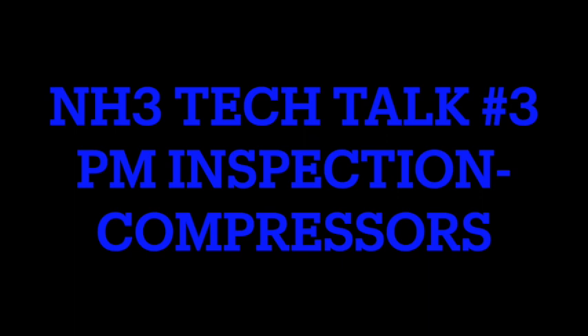If this compressor has an oil pump, a lot of compressors have an oil pump. Okay. Is it a full-time pump? Is it always running? Or is it a part-time pump? Does it kick on to build up oil pressure and then the compressor starts and then uses the pressure to provide oil flow? These are all things you got to know. If it does have an oil pump, okay, is there an oil pressure regulator? There should be, or an oil bypass or something. You ask your journeyman how to run an oil pump without starting the compressor. This is very handy dandy.